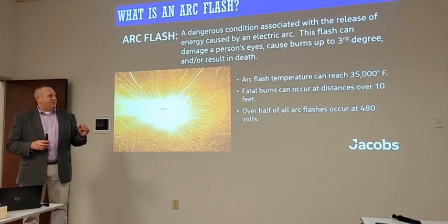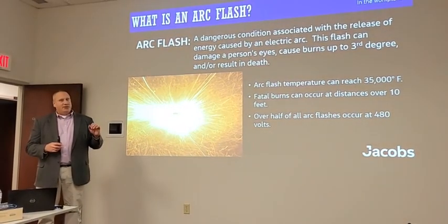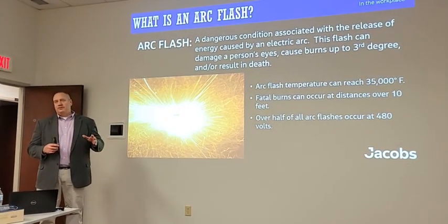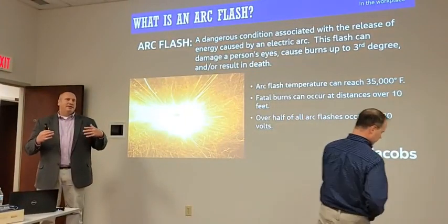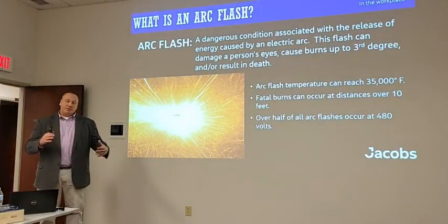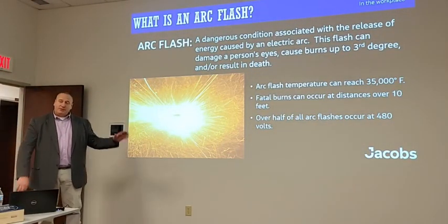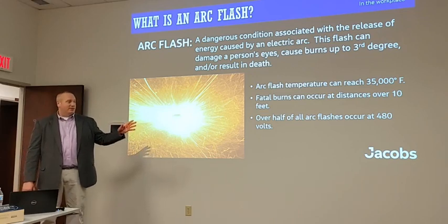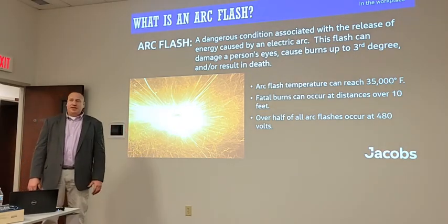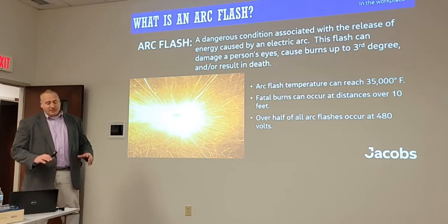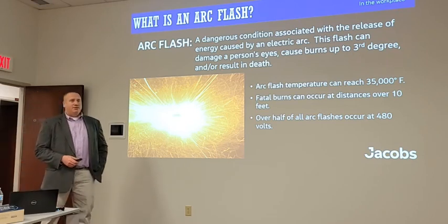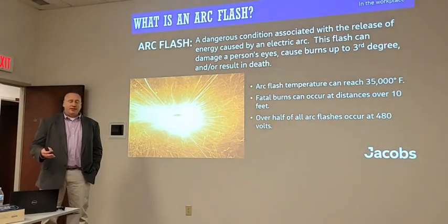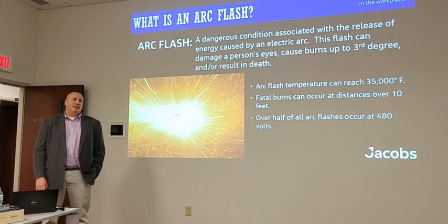And one common misconception is that arc flashes happen at high voltages. Being a power guy, the definition of high or low voltage stops at 600 volts, so 480 volts is still low voltage. I know a lot of folks out there consider 480 to be high voltage, but arc flash, as we'll talk about later on, is really voltage independent. It doesn't really matter. And actually 480 volts is one of the most dangerous classes of voltage when it comes to arc flash severity.